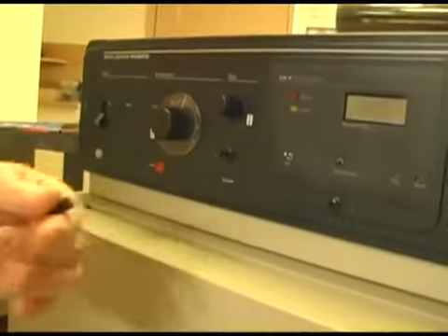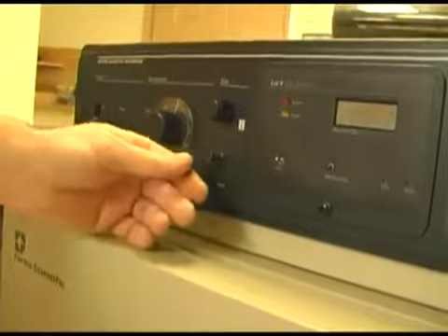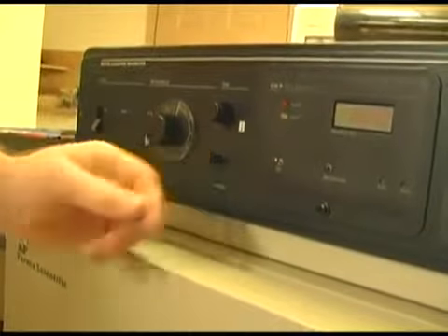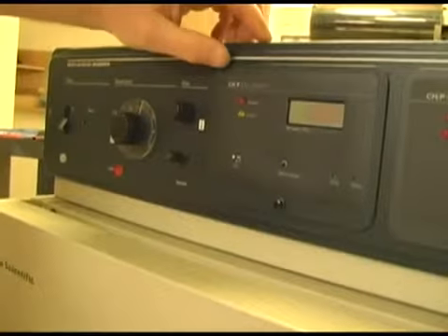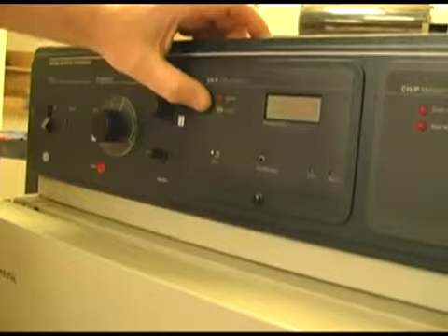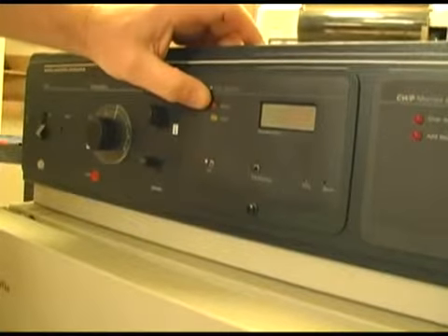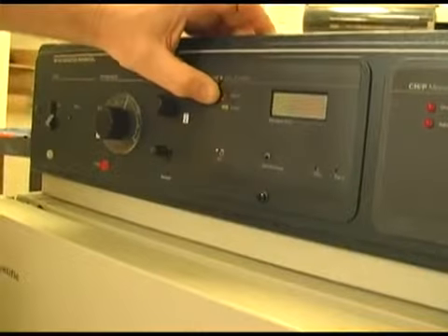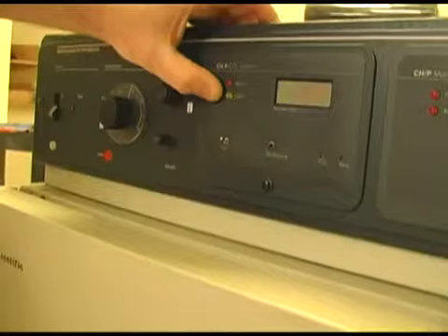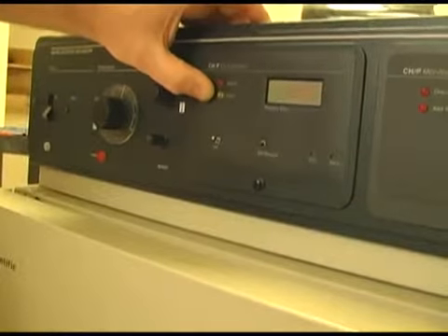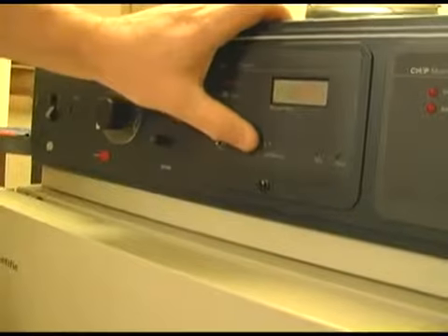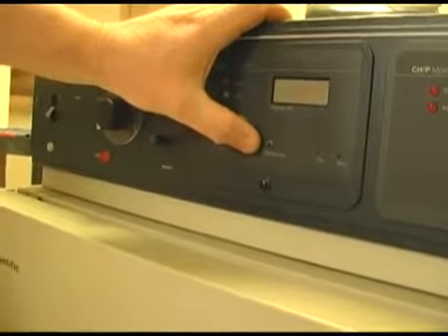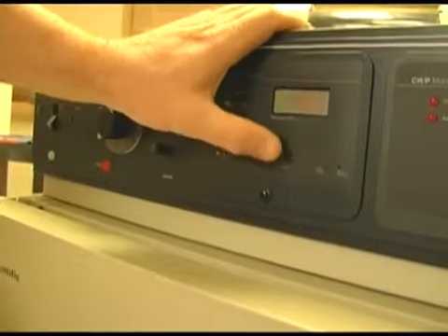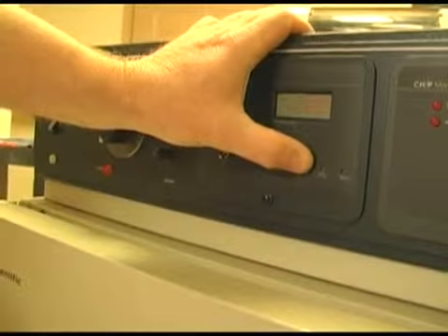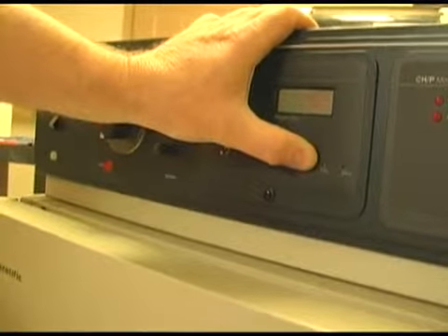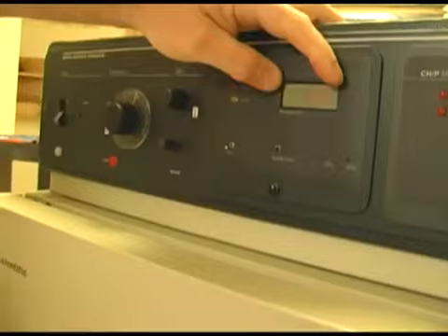Right here you have a sample port that goes directly into the chamber so that you can use a Fyrite to see what the percentage of CO2 is in your incubator. This is the CO2 control. You have an alarm. That's if your CO2 gets too high. You have an inject LED. When that's lit, it tells you that the instrument is calling for CO2. You have an on-off switch. You have a set or silence. By pushing it, you can silence an alarm. By pushing and holding it, you can change the set point of your CO2. Through that, we're using that screwdriver. You've got a little pot here that you can use to change and set your CO2 set point. And also you have a spot here to zero it. And of course you have your display.